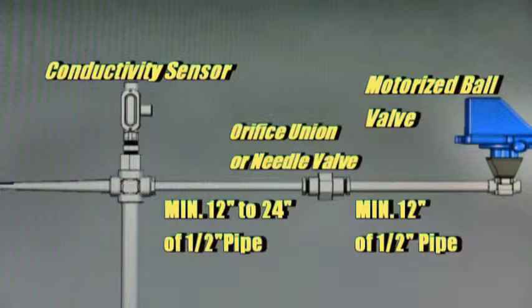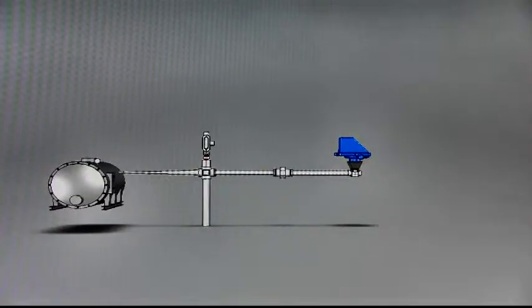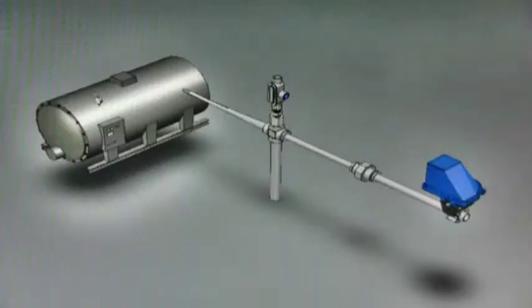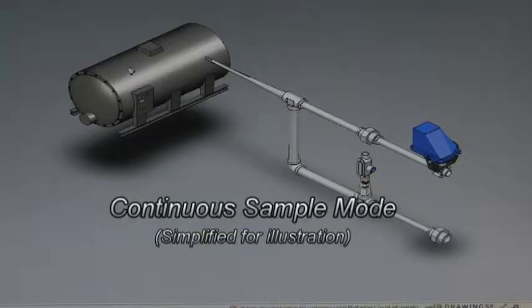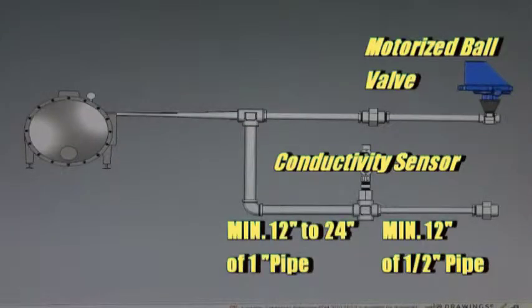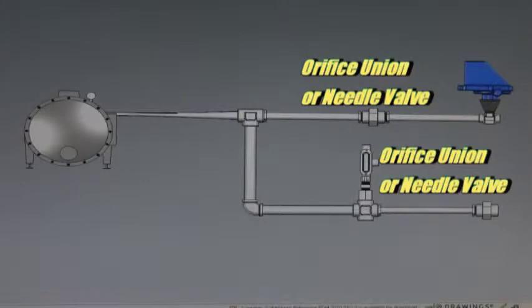Next, install a minimum of 12 inches of half-inch pipe from the conductivity sensor over to the orifice union or throttling valve. Then install another 12-inch piece of half-inch pipe over to the motorized ball valve. Maintaining these pipe diameters and distances will ensure optimum performance of your system. Installation of the probe in a continuous sample mode is very similar to the time mode. Run a 12-inch piece of 1-inch pipe before the sensor and a 12-inch piece of half-inch pipe after the sensor.